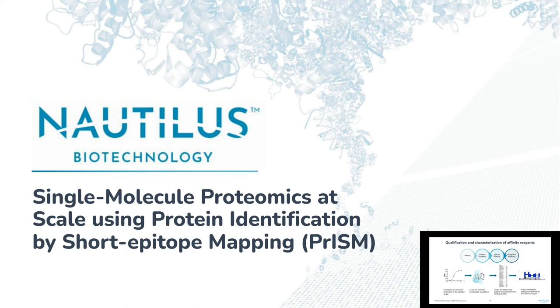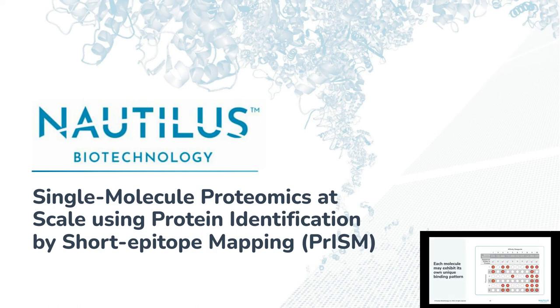One of the key questions of the platform, and one of the key attributes that one needs to address, is that this is a single molecule platform with a tremendous amount of stochasticity. Consequently, there is not a single canonical fingerprint that one might anticipate. It is likely that every single molecule will have a series of different bindings from each reagent, and really we're asking the question, given an observed pattern of binding, what protein is compatible with this pattern of binding? We're not anticipating a singular pattern for any given protein. And this is why there is a sophisticated machine learning framework under the hood of PRISM.